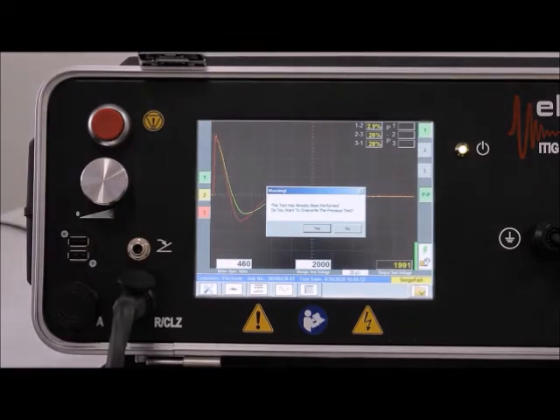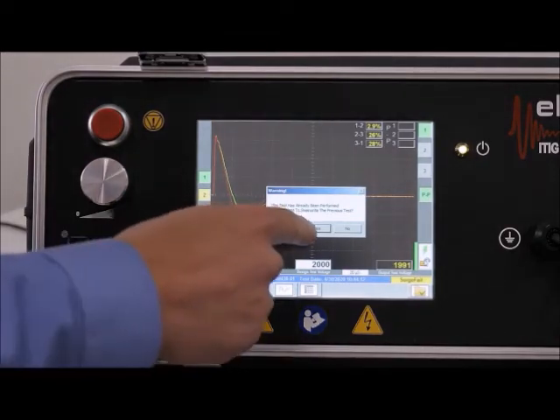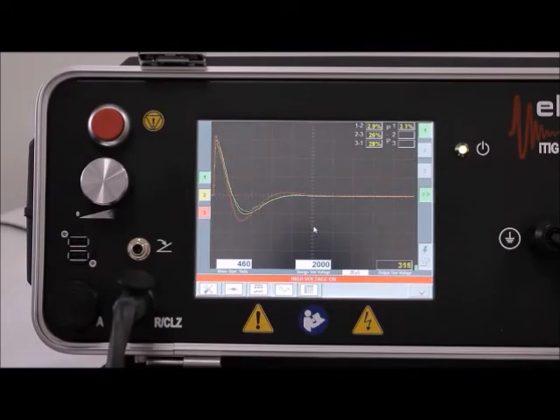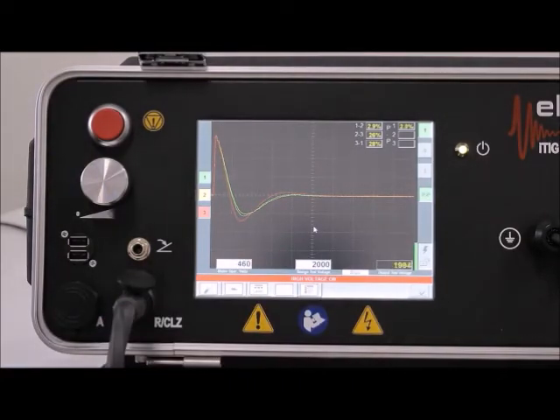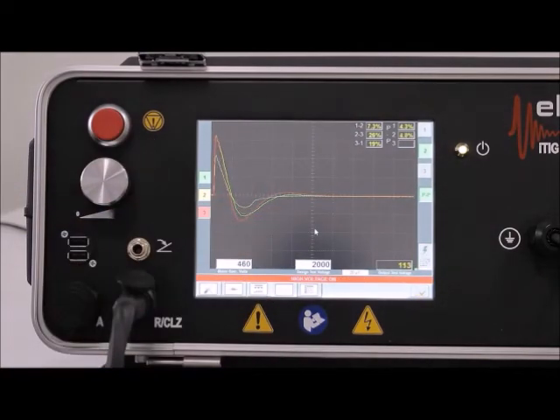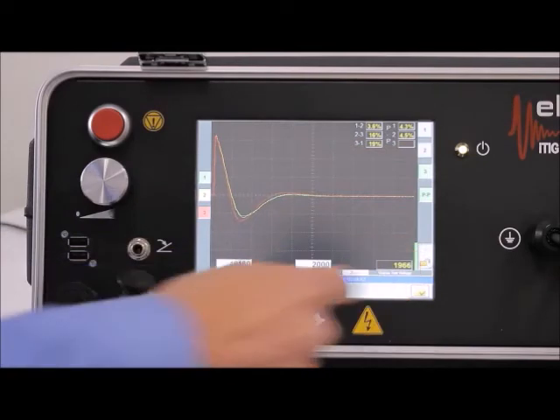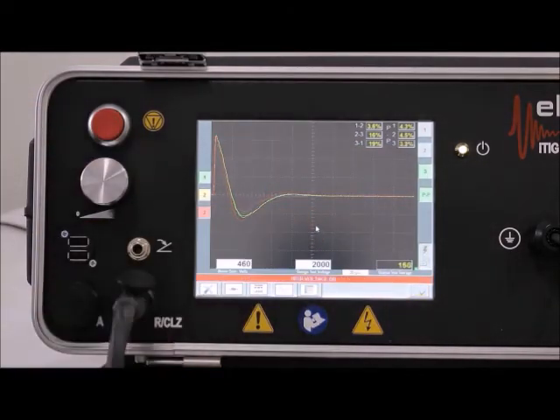The instrument will now ask if I want to override the previous test set. I'm going to say yes. We're now going to start at a very low voltage, approximately 50 volts, and we're going to step it up at 25 volt increments all the way up to our 2000 design test voltage. We're going to do this in all 3 phases. What we're now doing is comparing each individual phase to itself throughout this voltage range. If anything happens, we will have a sudden change from one step to the next, indicating that we have a turn-to-turn, coil-to-coil, or phase-to-phase insulation issue.